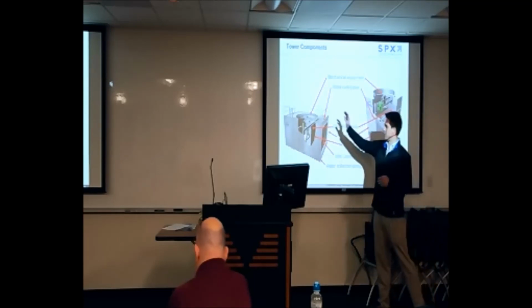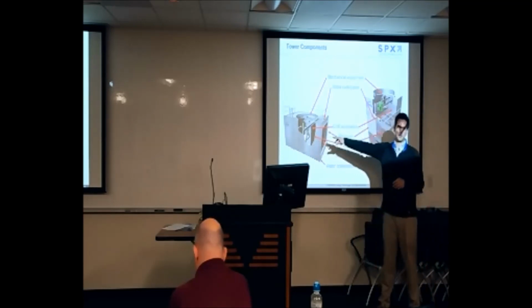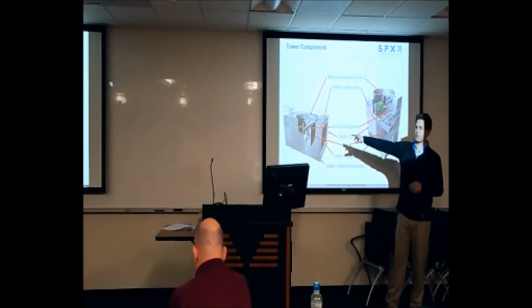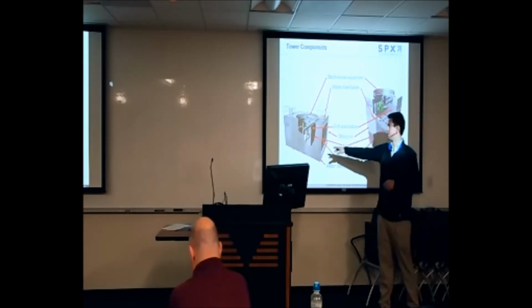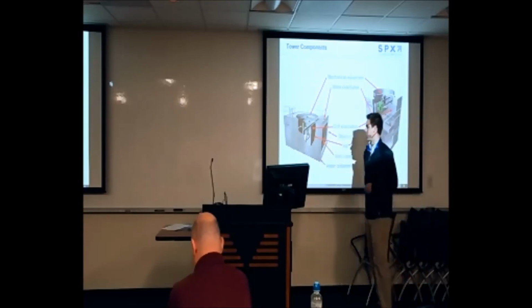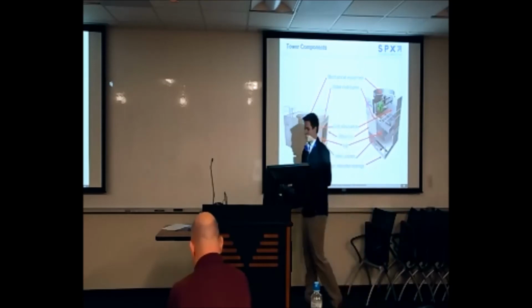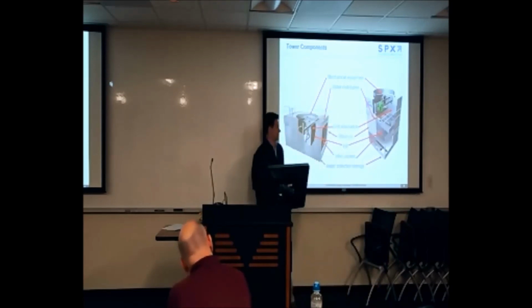On the other side of the fill, you have drift eliminators. What do you guys think the purpose of the drift eliminators is? It is to eliminate drift. That's what drift eliminators do. So yes, not getting the motor wet is one purpose. But these fans are pretty powerful, and they can actually pull up some of that water that's in the system and blow it out into the air.